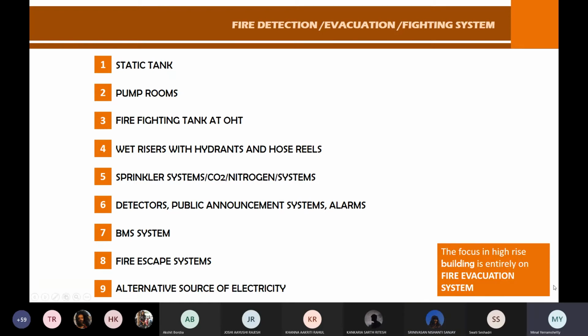What could be the reason? Maybe because the lift is not supposed to be used during a fire event. If smoke goes there, or else the shaft acts as a chimney and smoke can rise within it. So the reason for keeping it negative is, as you rightly say, that certain lifts will not be allowed for people to use to evacuate. Those lifts which are not going to work as evacuation lifts will have negative pressure. The rest, which actually take people up and down, generally service lifts, will be used because service lifts are larger and can take more load.